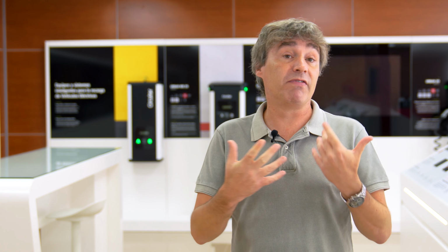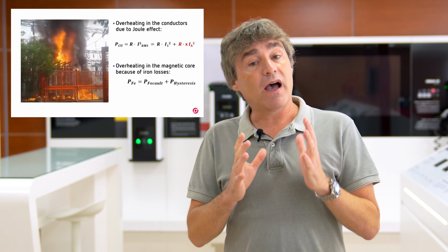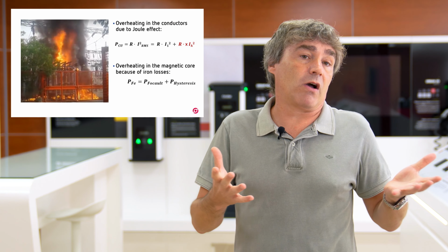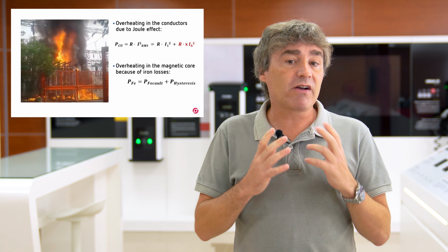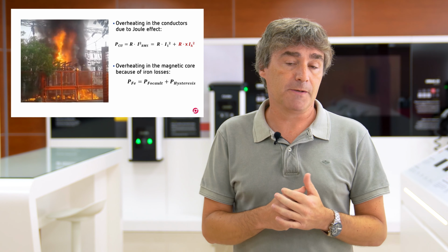Troubles can also happen in the power transformers, since if they, besides supplying the fundamental current, that is the active and reactive power demanded by the loads, also have to supply harmonic current, their internal losses are also increased, either due to Joule effect, the copper losses, or mainly the iron losses, because these are directly proportional to the frequency.